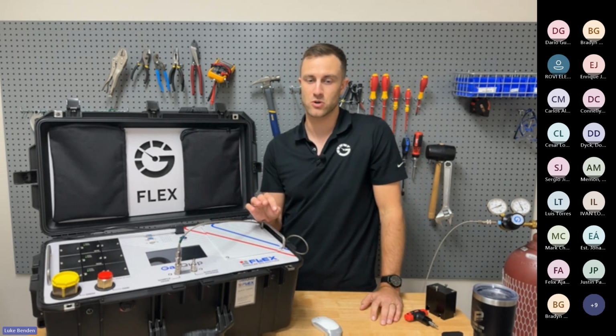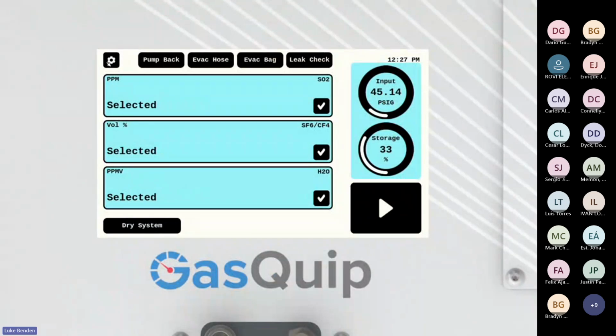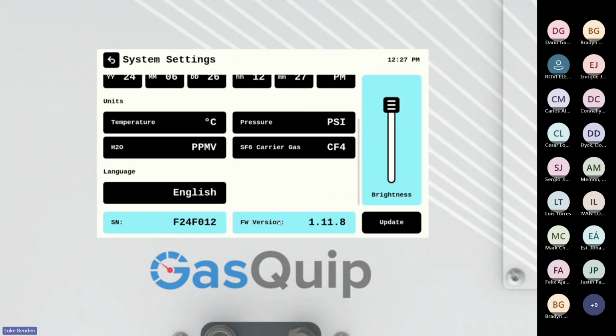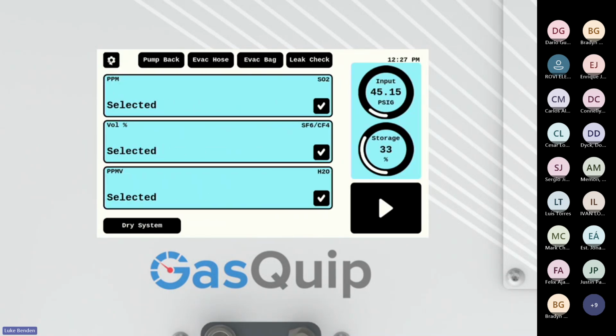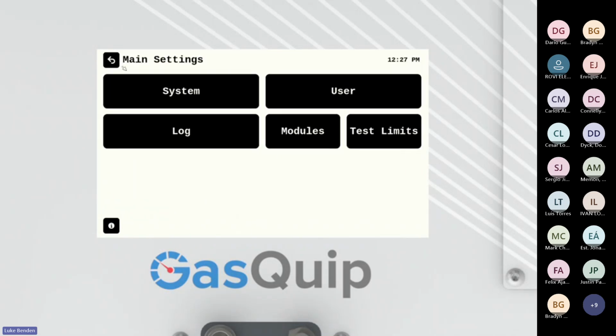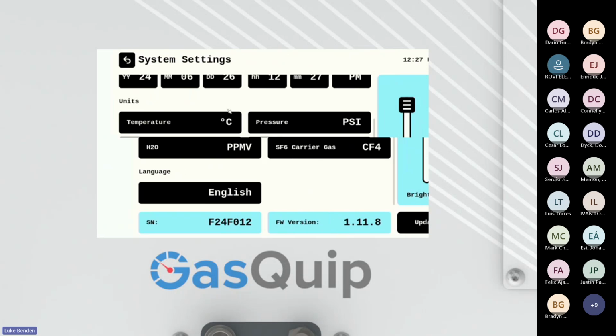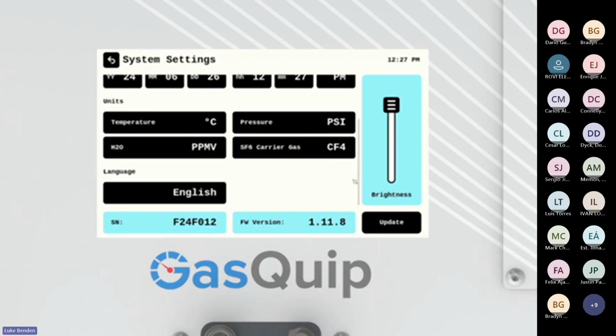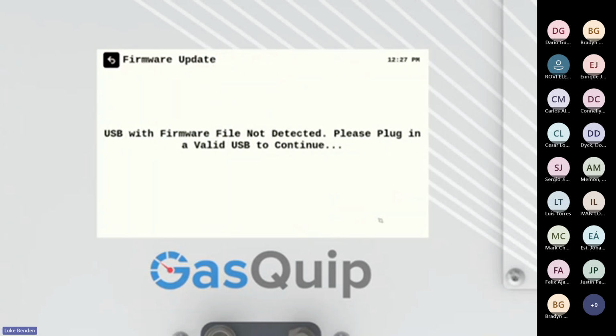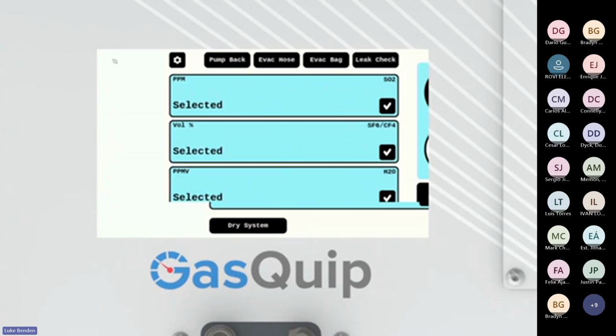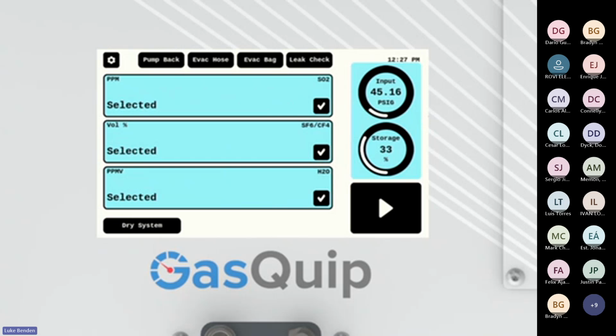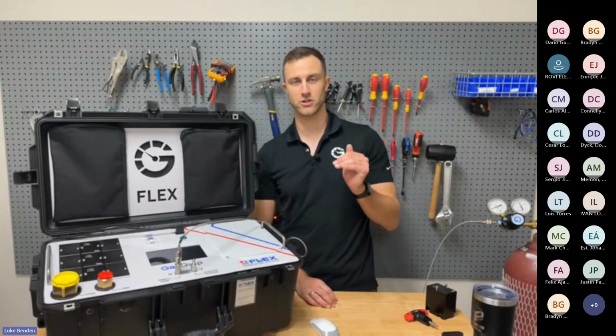Check the firmware. You can go into our settings, system, and then firmware version. Make sure that's the current firmware. You can give us a call or email us to see if there's any updated firmware that needs to be loaded onto the system. Really easy to update the firmware or software if you need to. You just plug in a USB stick that has the file that we send you, plug it into the device, and click update, and it will automatically grab that file and restart the device with the new firmware.